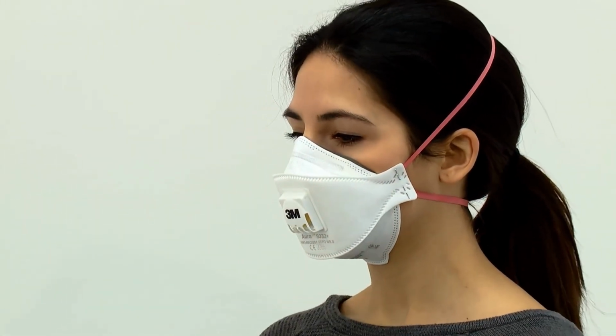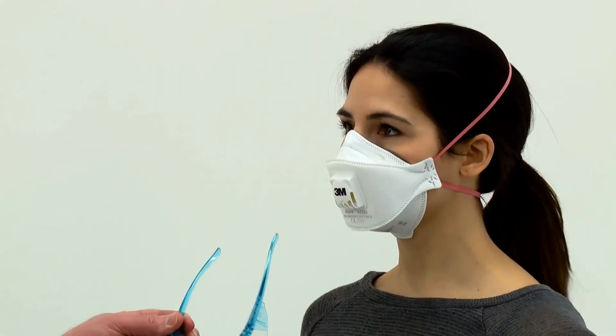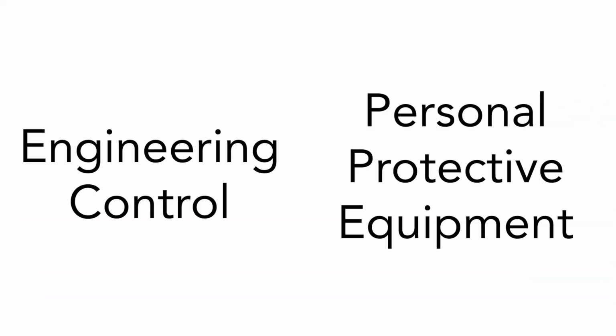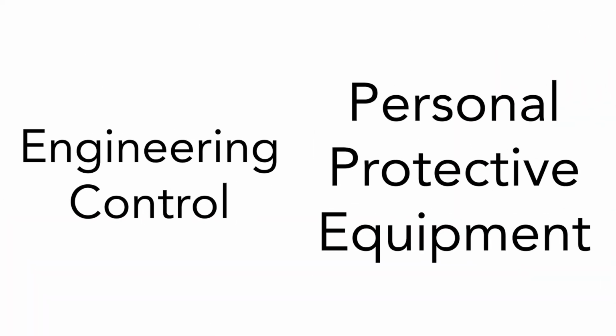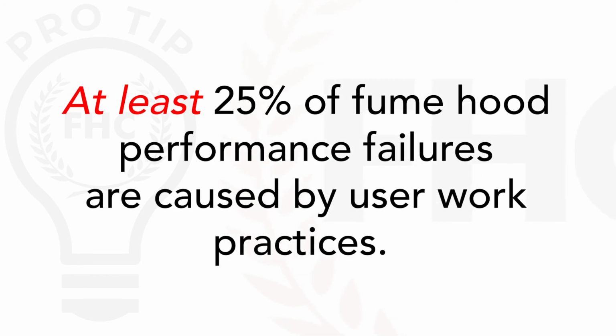PPEs, as simple as an N95 mask, require fitting and training. So why not a fume hood? The answer comes back to that hybrid nature of the hood. It is more often classified as an engineering control rather than a PPE. As such, a hood's performance is often considered outside the control of the user. Yet, after testing thousands of hoods, we know that at least 25% of fume hood performance failures are caused by user work practices. As a user, you're an important part of the system.